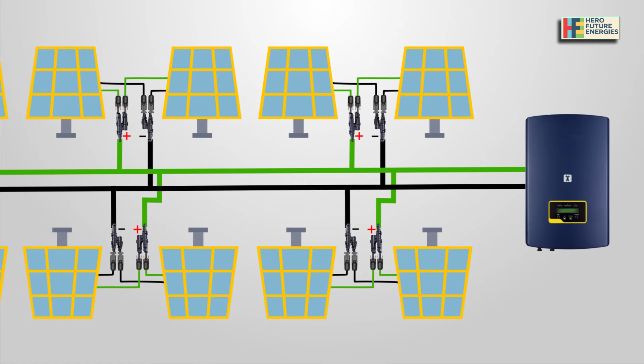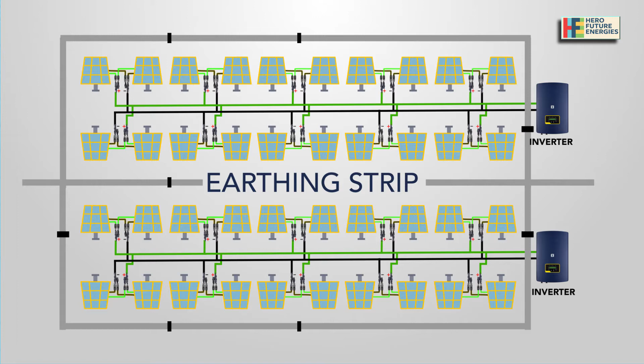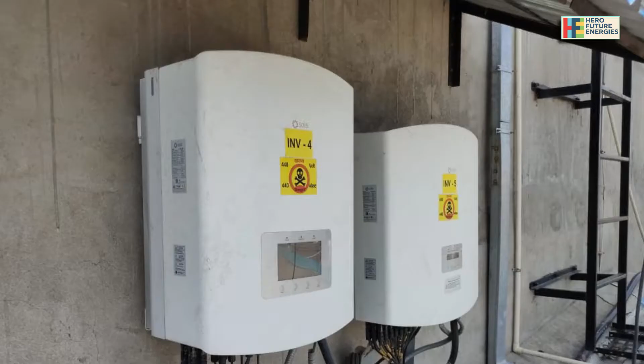Cable tray installation must always start from one end. A separate earthing strip is led along the cable tray runner, and all other trays and earthing strips should be interconnected. The earthing strip is fixed by welding at every 1.5 meters. As an industry good practice, always apply GI paint at cut and welding points of cable trays.